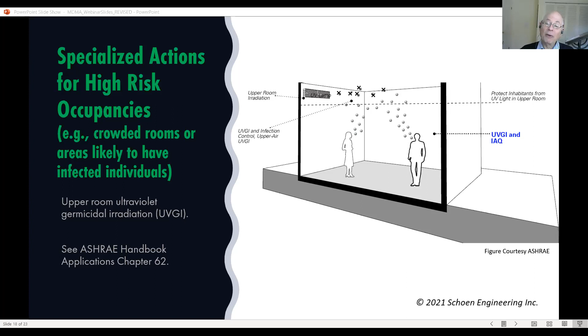So that's why I'm showing the upper room. Now, where would I use this? Frankly, in a hospital waiting room, a healthcare or transportation waiting room—someplace with large occupancy, unknown risk, lots of flow of people in and out, where I want to supplement ventilation. Ironically, these systems work better in rooms with lower ventilation rates, because if you already have a higher ventilation rate and better filtration, you're doing so much that ultraviolet can't add much more.